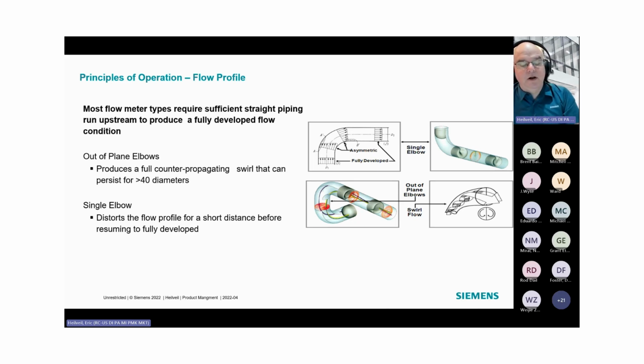So the solution for that is we call it a disturbed flow profile adjustment. There's a number of different names for it. But basically what it does is it allows the user to install the transducers where they have the room. And if you have some bends and if you have an expander or a reducer, you can tell the transmitter, hey, this is the setup I have. I don't have the proper 10 before and 5 after, or 20 before or 5 or 10 after. You can tell the transmitter I have a disturbed flow condition. And what the meter does internally is correct for that and will actually help digitally laminarize the flow, calculating that with an algorithm. It's built into all the transmitters, by the way.